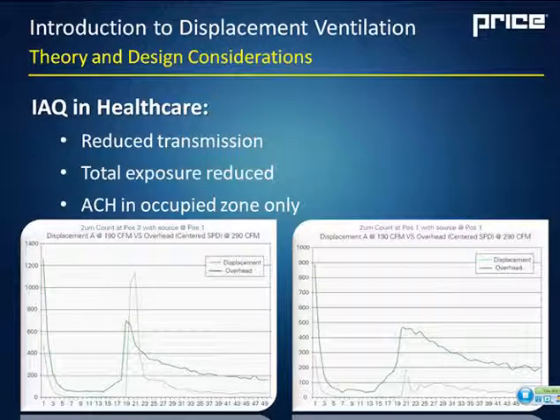Now a quick discussion on some of our research in indoor air quality in healthcare. What we've seen is reduced transmission, and the exposure is reduced for a person entering a patient room. So the two graphs on the bottom here are showing a sneeze. In this case, a mannequin is lying in the bed, and we've simulated a sneeze, and the measurement is taken at the caregiver's breathing zone, which is standing right beside the bed. The one on the left is with the person sneezing towards them, and the one on the right is with the person sneezing up in the air.